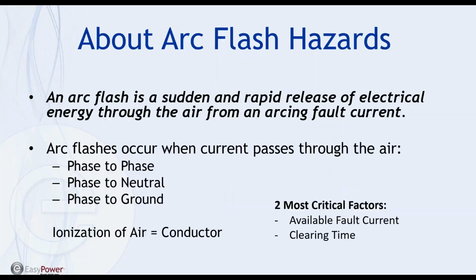Just a little one-on-one on arc flash: an arc flash is a sudden and rapid release of electrical energy through the air from an arcing fault current. That fault current could occur phase to phase, phase to neutral, or phase to ground, and it's conducted through the ionization of air. The two most critical factors in an arc flash are the available fault current and the clearing time.